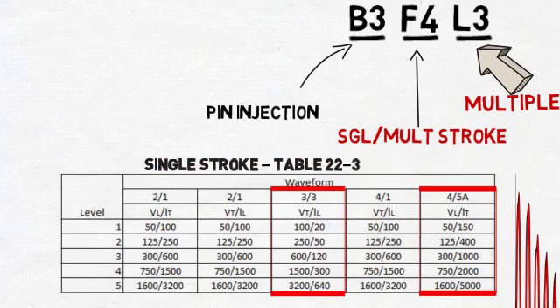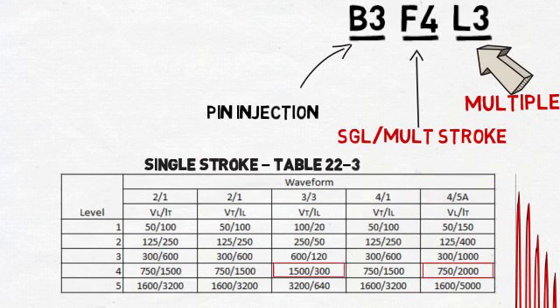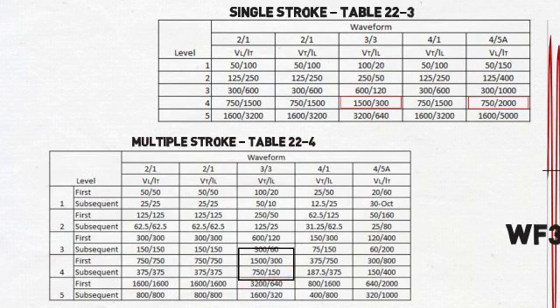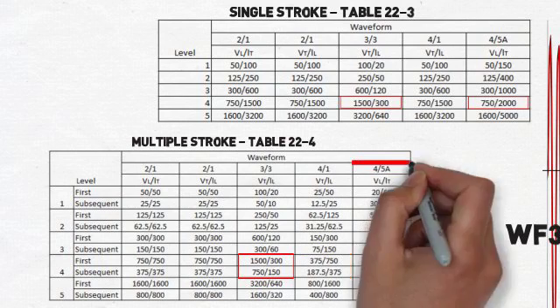Using level 4 for our waveform test level, we can see single stroke is tested at 1500 volts and 300 amps, while waveform 5A is tested at 750 volts and 2000 amps. For waveform 3, the first stroke in multiple stroke is tested at 1500 volts and 300 amps, while the subsequent strokes are tested at 750 volts and 150 amps.